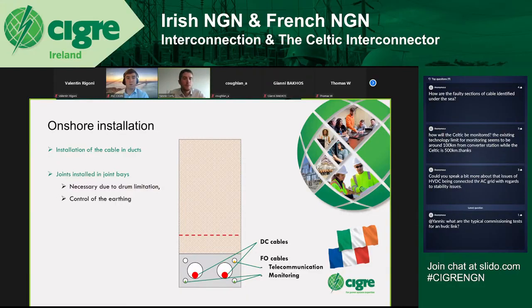Those are necessary due to drum limitation. You can't move 30 or 40 kilometer drums, and it's also needed to control the earthing of the cable screen. When you have a failure, you can have over voltage of the cable screen that can damage the other layers. So you need to earth it from time to time to control it.